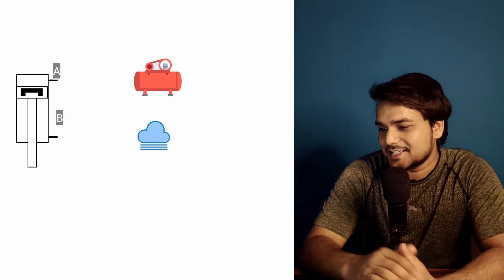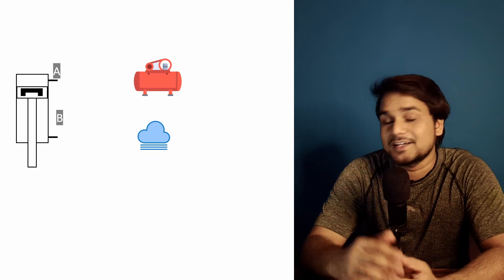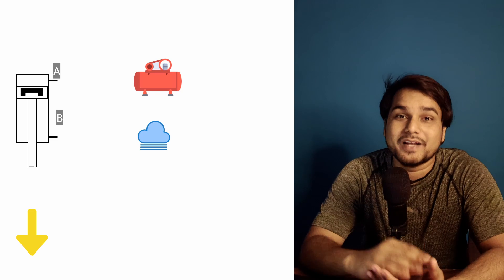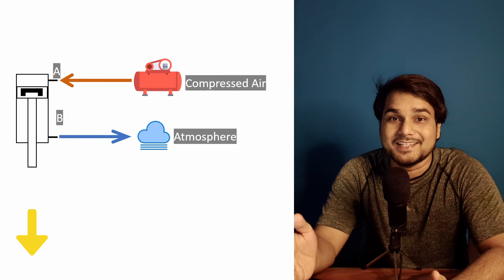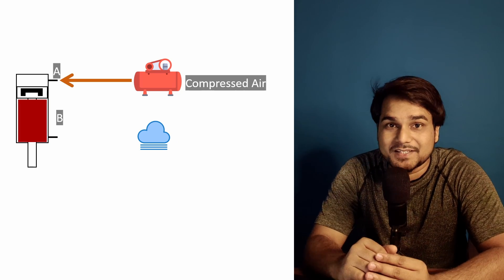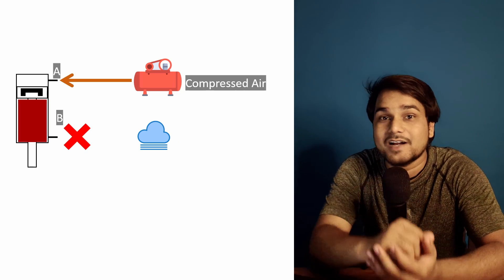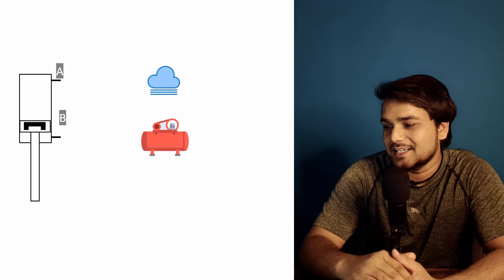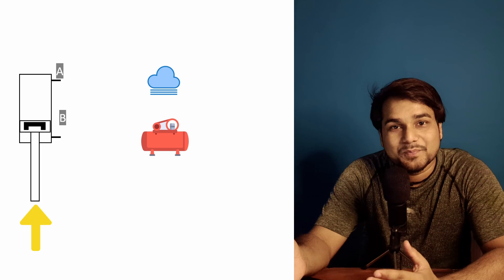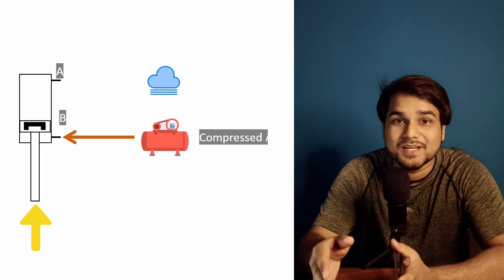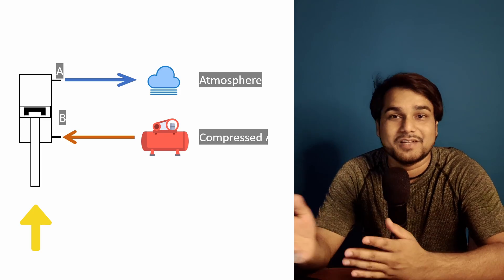Let's start with the very basics. If we want to operate the pneumatic cylinder downward, we connect the compressed air supply to port A and set port B to exhaust. Otherwise, if the air below the piston will not release, it will not let the cylinder come down. In the same way, if we want to move the cylinder upward, we connect the compressed air supply to port B and at the same time set port A to exhaust.